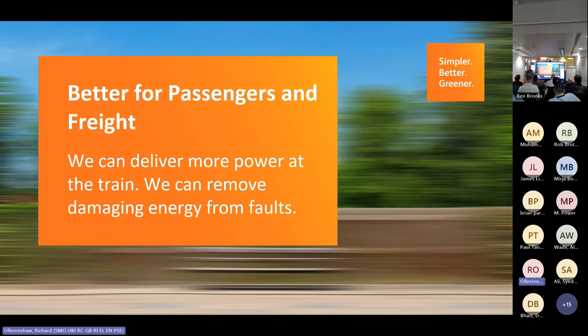We cause massive amounts of unbalance for them. We take off one phase, they supply three phases. We put our return current through their system. They like balance. They like to have phase and phase current. They don't like to have return. And that's reflected in our standards and our processes with GRID. We've got a 129-page document just for railways that covers off how we work with our distribution companies. And we've got an additional 169-page document called NSI 26 that's just for how we work with National Grid at our sites at 400 kV. And we've got fewer than 10 people in the entire country who are actually competent to execute those NSI 26 instructions and deliver isolations for us. So that gives you an idea about how non-standard we are.